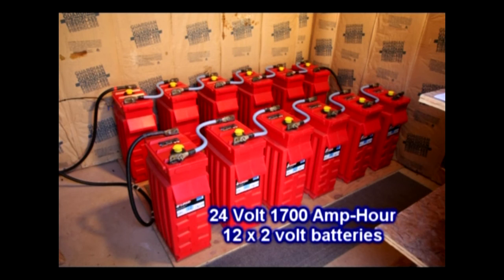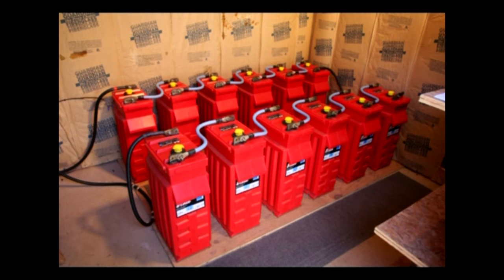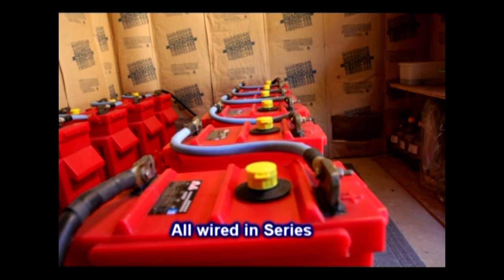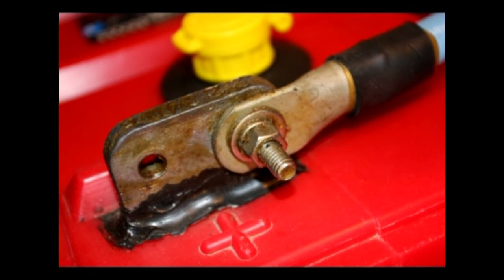The battery bank is a 24 volt system built with 12 2-volt, 1700 amp hour Rolls-Surrette solar design batteries. These are really the top shelf industrial batteries specifically designed for solar applications. Each one is wired to the next, negative to positive, forming a series battery bank at 24 volts. Extra flexible double-aught cable is connected to each post using traditional hardware, and non-ox compound has been put over the connection to keep it from oxidizing.